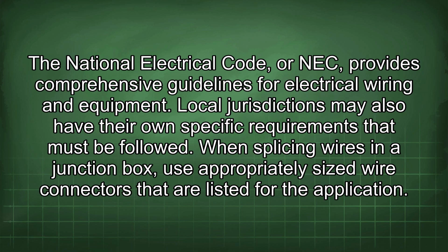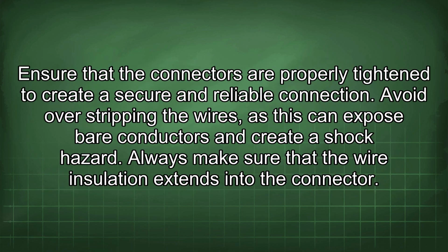When splicing wires in a junction box, use appropriately sized wire connectors that are listed for the application. Ensure that the connectors are properly tightened to create a secure and reliable connection. Avoid overstripping the wires, as this can expose bare conductors and create a shock hazard. Always make sure that the wire insulation extends into the connector.